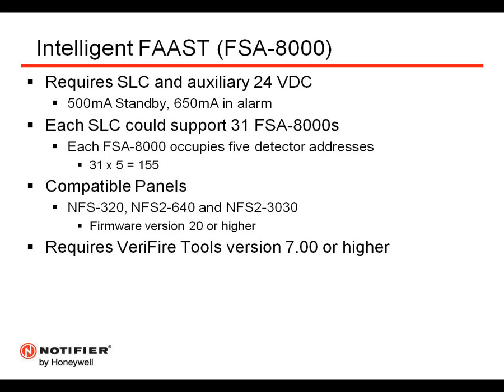What panels is Intelligent FAAST compatible with? It's compatible with the NFS320, the NFS2640, and the NFS23030 operating with firmware version 20 or higher. And just in reference to version 20, we expect to release a firmware version 20 for our current ONYX series panels next week. We'll require VeriFire Tools version 7.00 or higher in order to configure panels that have version 20 and in order to do the programming parameters for Intelligent FAAST.